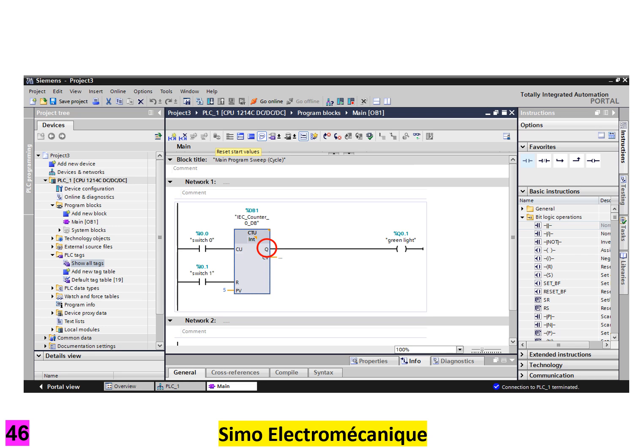CTU stands for count up. In operation, CTU counts the number of times input CU is switched on. Once the counter reaches the value in PV, preset value, output Q is switched on. To reset the counter back to 0, input R must be activated. Output CV can be used to read the current count value to trigger other events at certain values.